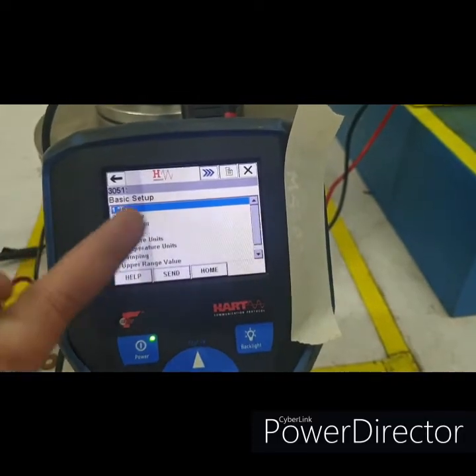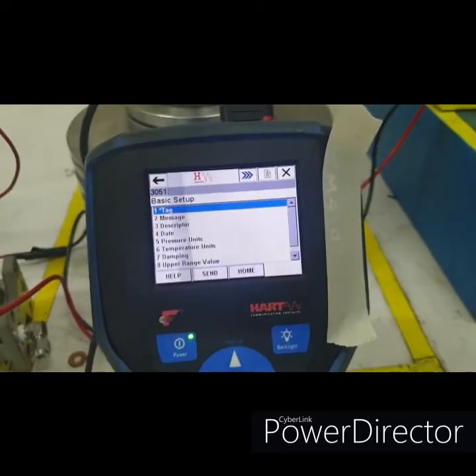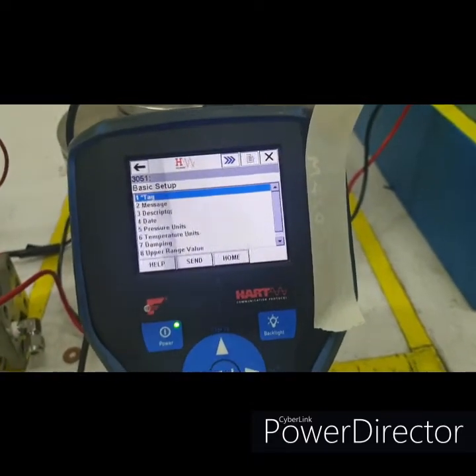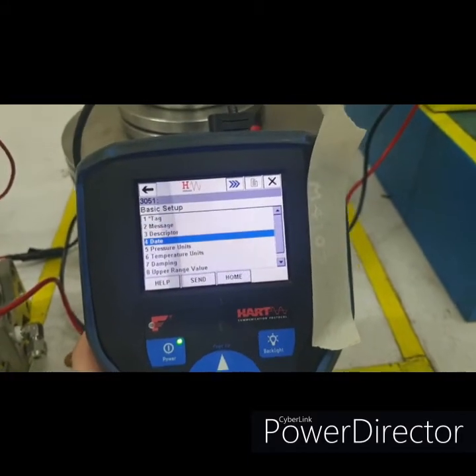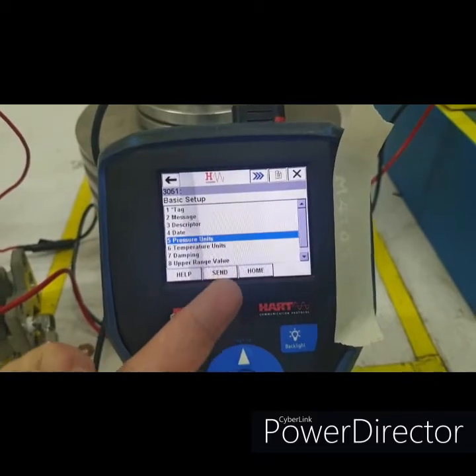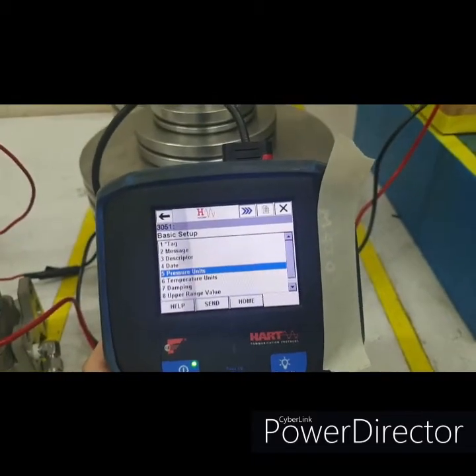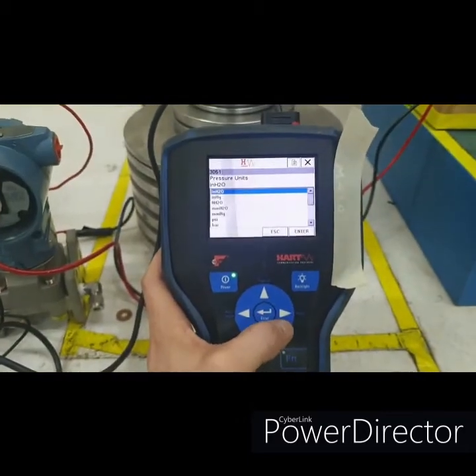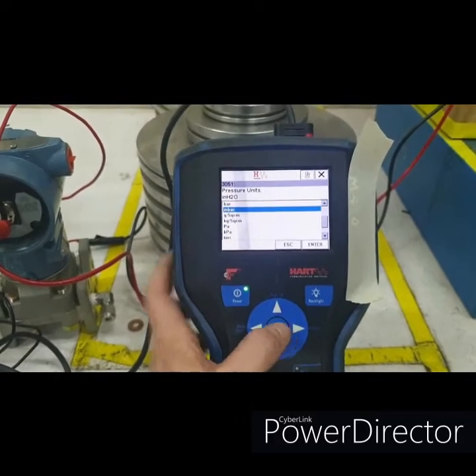If you want to download that configuration to the transmitter, you will press send. But since we have to change multiple parameters, we will change the other parameters. Let's say pressure units, because the default is in inches H2O, we're gonna change it to millibar. So we'll select millibar.